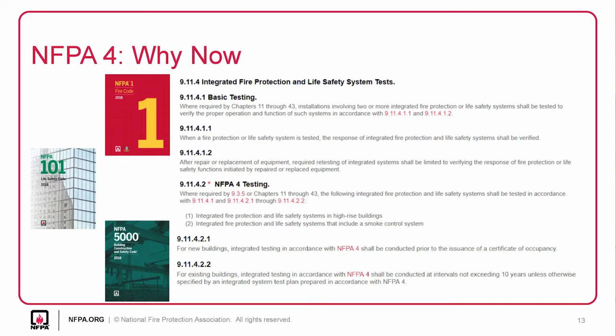But now we've got NFPA 4 testing. NFPA 4 testing is you need to follow the procedures within NFPA 4. So you need to have an integrated testing agent, you need to have a team, you need to document it all per NFPA 4. That's if you have a building with a smoke control system as one of its integrated systems, which a smoke control system is an integrated system itself, or you have a high-rise. If you have either of those buildings, you're required to do integrated testing per NFPA 4. And essentially you need to do that before you get your certificate of occupancy.